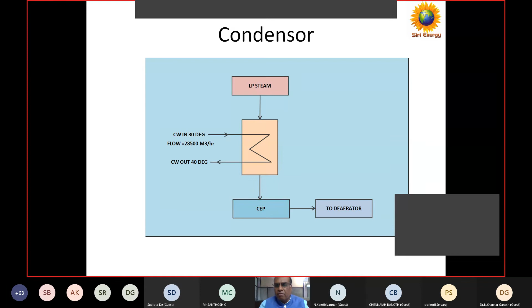Just for the purpose of analysis, I will give one Excel sheet where I am giving the condenser performance. Though I said condenser performance is for a 210 megawatt unit, this is recent data from one of the power plants we audited. So you can see the actual generation is varying: 170, 185, 160, 163 - they are operating at low load.